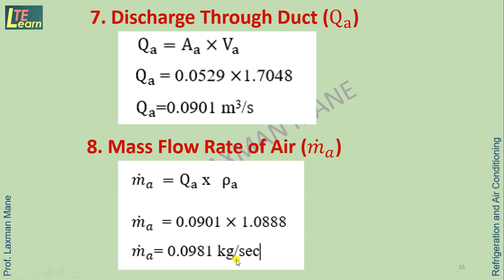Refrigerating effect, meaning cooling effect, can be obtained by using the formula mass flow rate of air multiplied by the enthalpy difference along the duct. H1 is the enthalpy of air at the inlet and H2 is the enthalpy of air at the outlet. So from the psychrometric chart, we take the values of H1 and H2, putting them over here with the value of MA. In the calculation we find the refrigerating effect here in kilowatt.